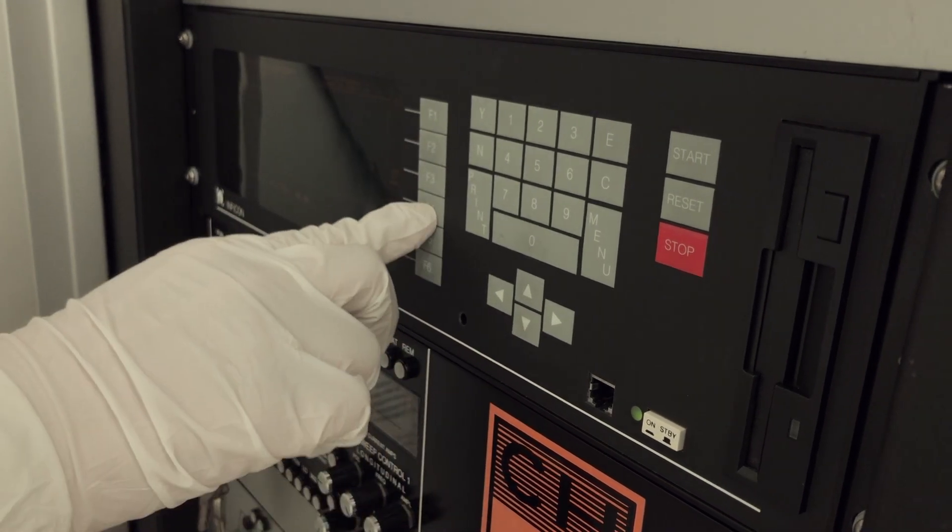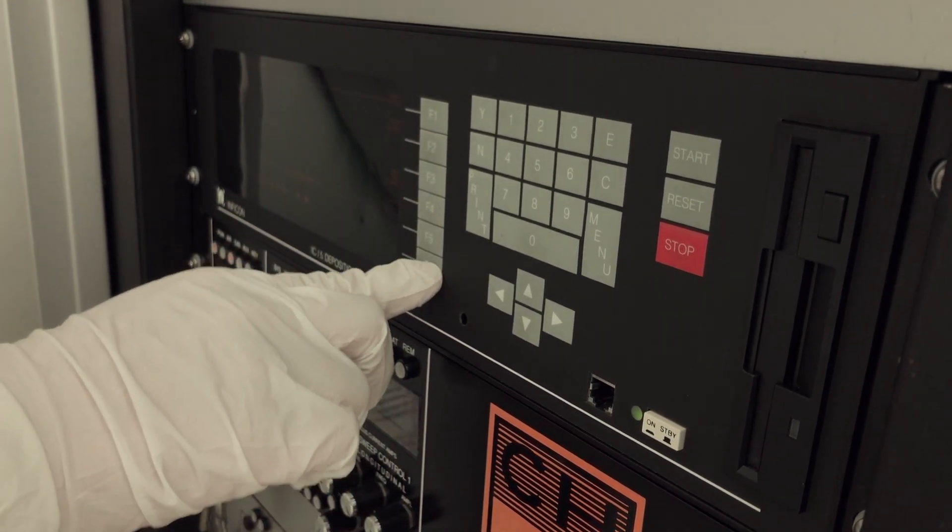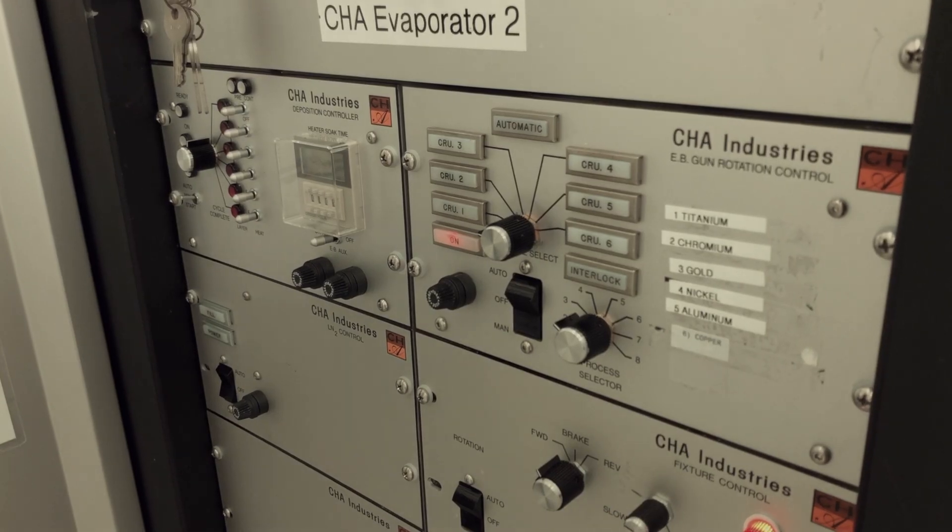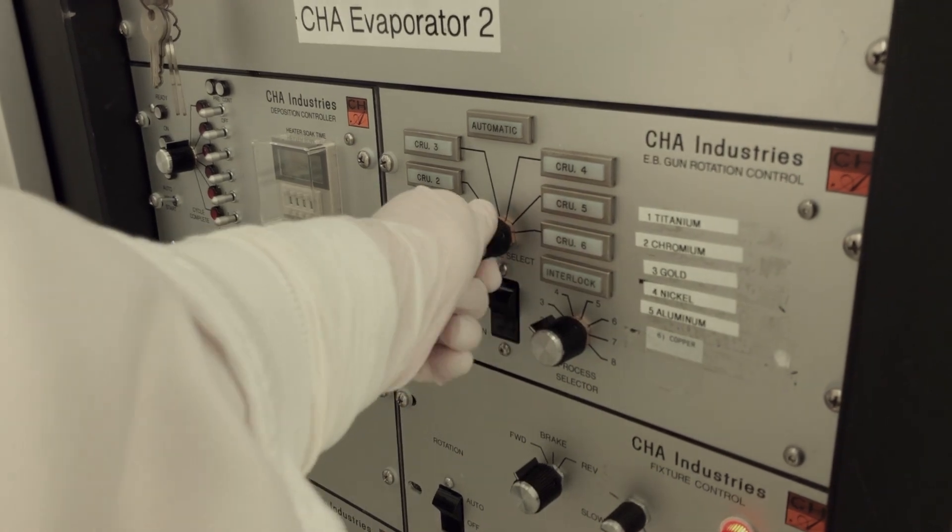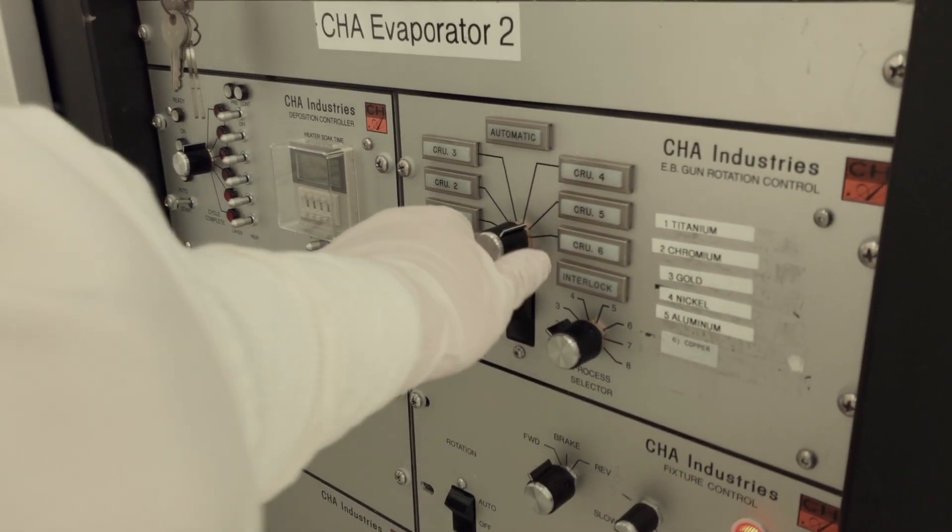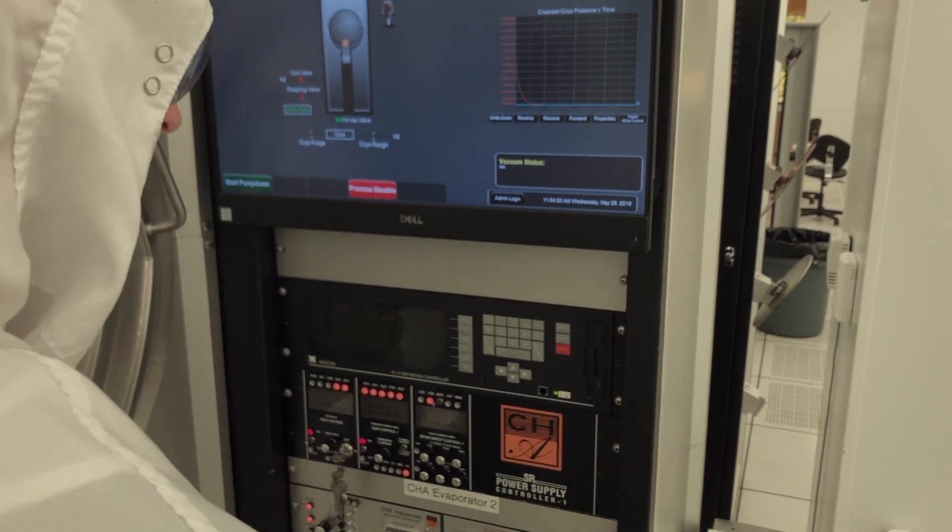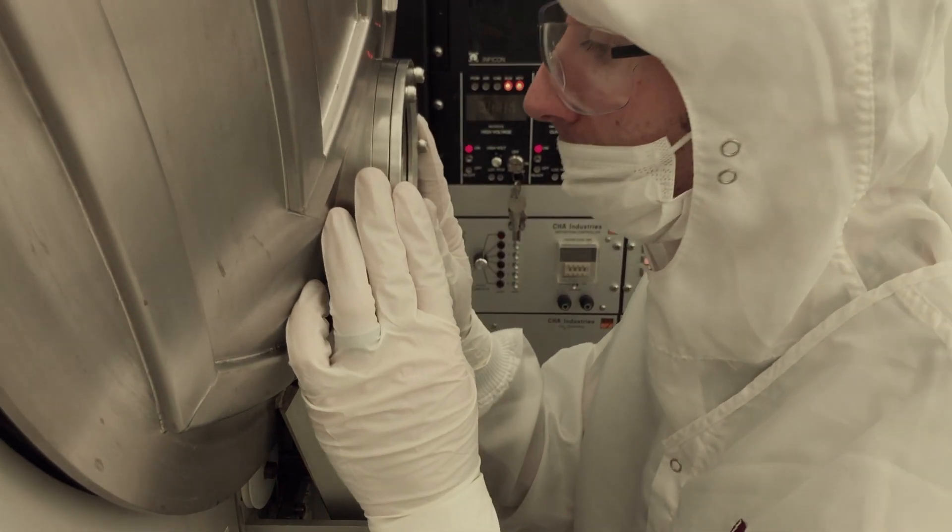Highlight the metal you want to evaporate next and press F4 for select active, then press F6, operate. Once your process has been selected, manually switch to the crucible that you want for your second layer. Once the process has been set up, press start on the deposition controller to begin running the process.